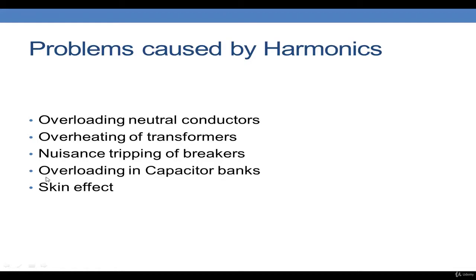Another problem is overheating of transformers. The no-load losses in transformers are mainly due to hysteresis loss and eddy current loss. Hysteresis loss is proportional to frequency, while eddy current loss is proportional to the square of the frequency. This results in additional no-load losses and also causes problems for motors.